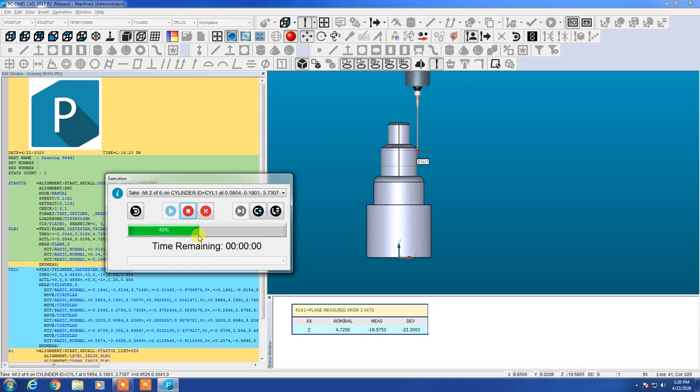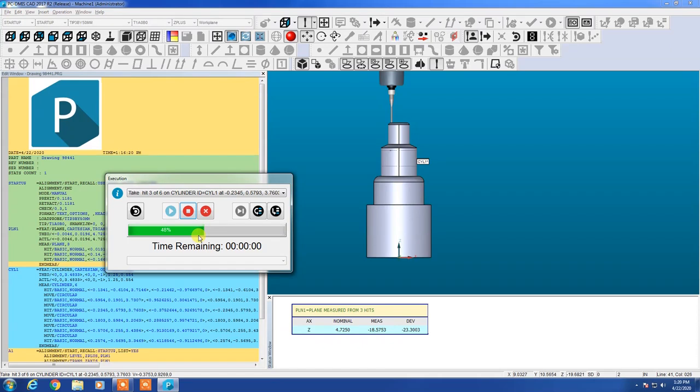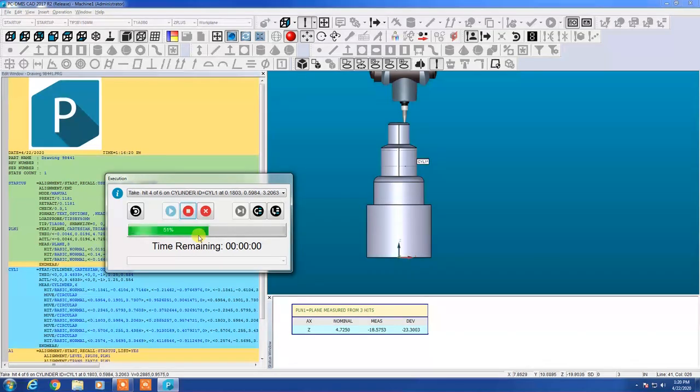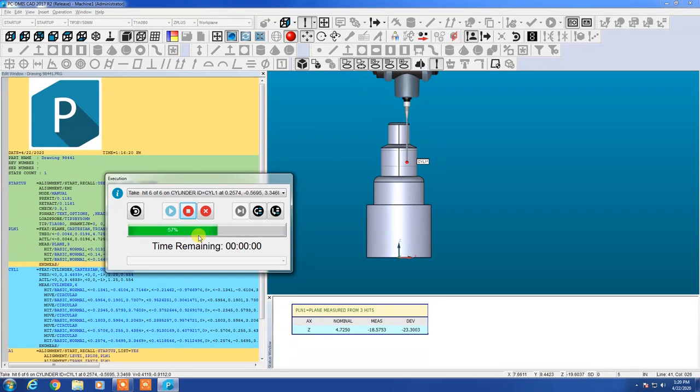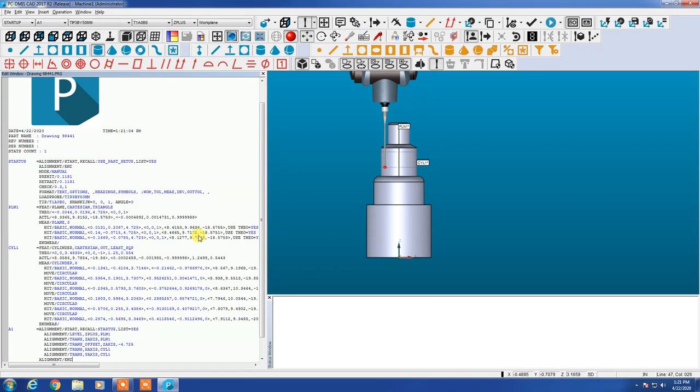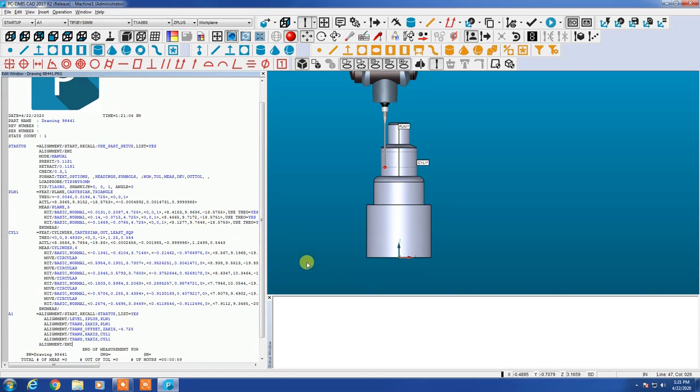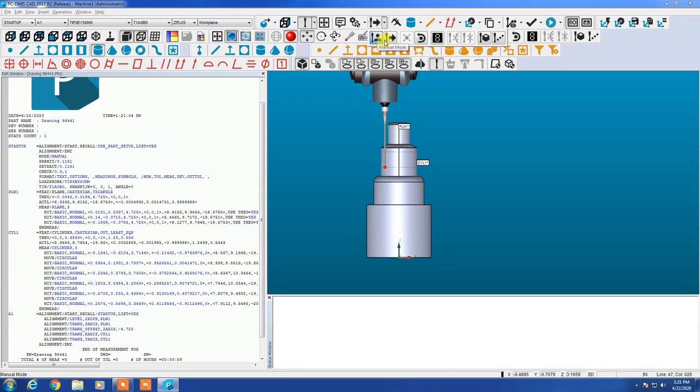Here we're going around the cylinder now. I'm making the measurements around on this part. And they don't have to be exact. They need to be sort of approximate. They show them in a particular order. It doesn't really matter as long as you cover those points legitimately. You hit them all and they're roughly where you said they were. They don't have to be exact. It's still going to capture the cylinder enough. The DCC alignment will cover this more substantially. So there we've completed it. Everything seems to be fine. Our trihedron didn't stray away from the part. So that's a good sign.